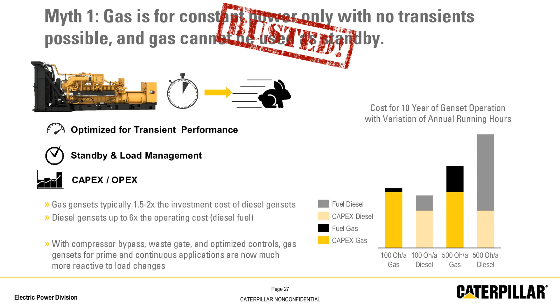So the more the gensets run, the more likely it is that a gas genset is less expensive over a typical operating period of, for example, 10 years. This is shown as an example on the right for comparable gas and diesel gensets at different annual running hours: 100 annual operating hours, like standard standby, and 500 annual operating hours, like standby that also takes over load management operations.